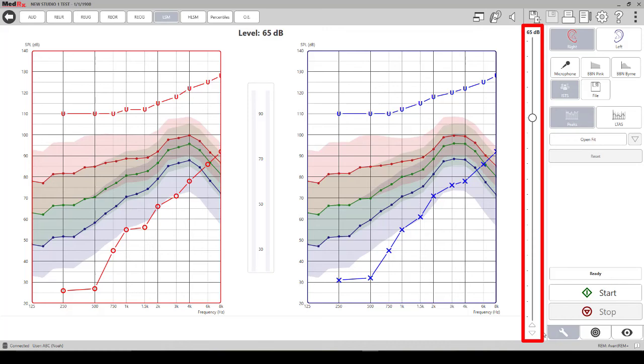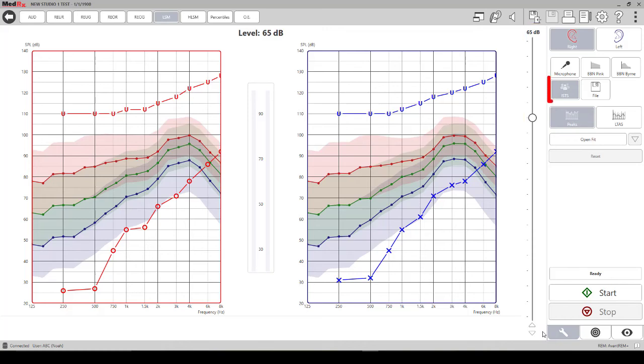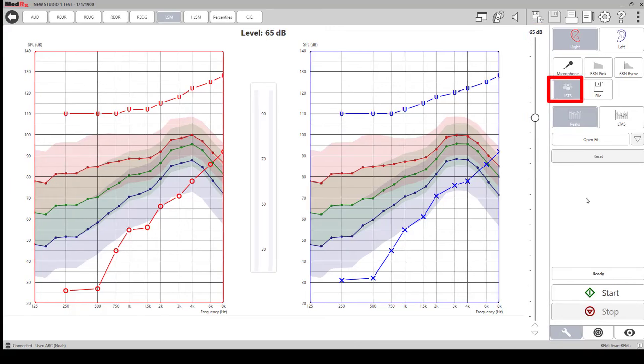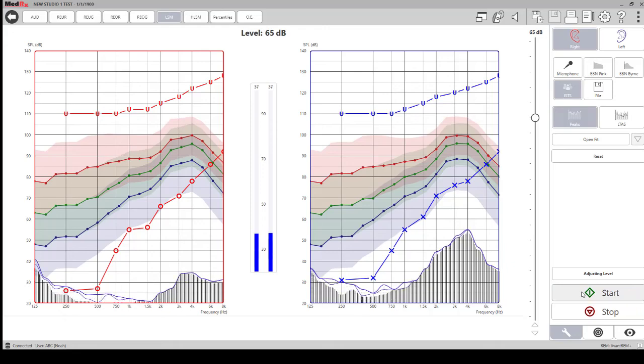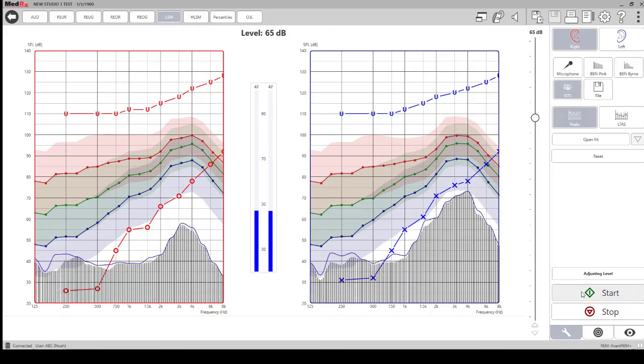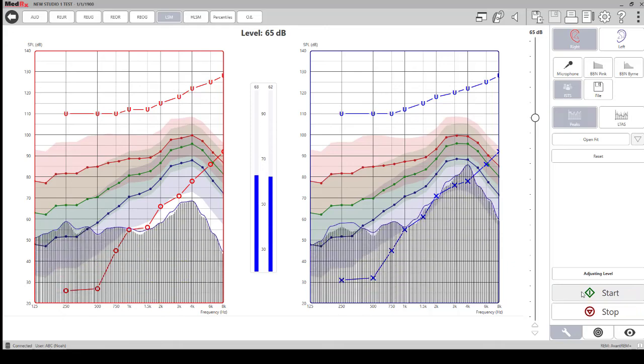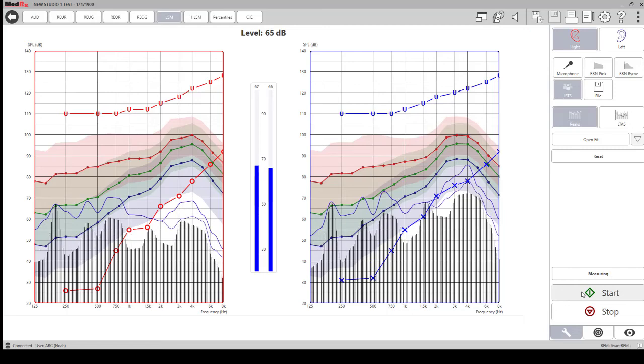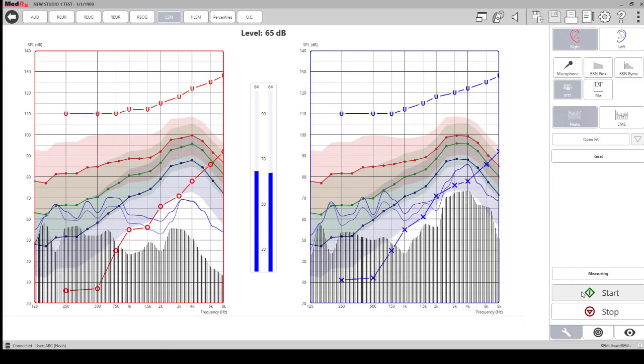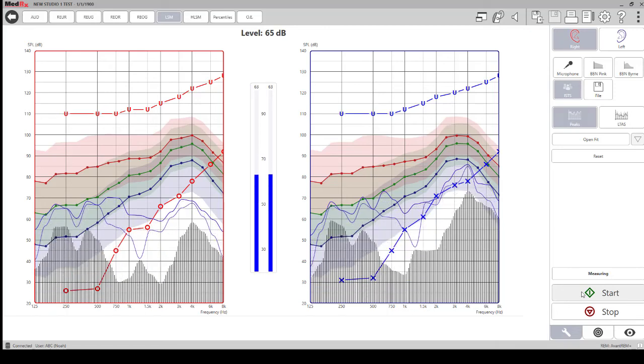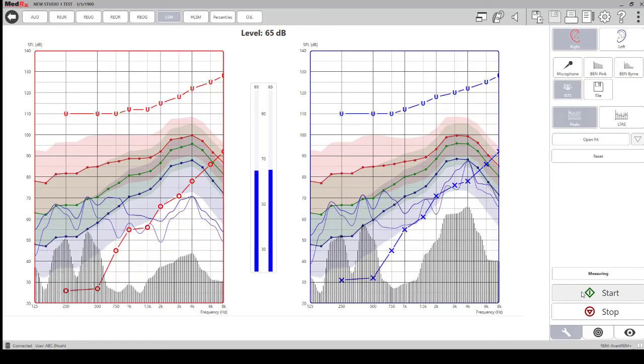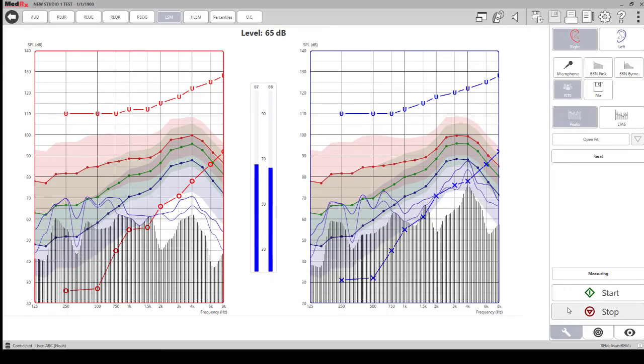For live speech mapping, it is typically run using the ISTS stimulus. To begin taking measurements, click the start button. When the stimulus is playing, you can go back to the manufacturer software to make adjustments to the settings so that your curves fall as closely as possible to the targets on the graph for each intensity level.